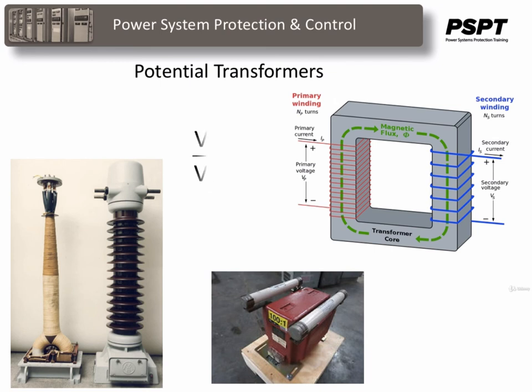Potential transformers. In general, the secondary voltage is proportional to the ratio of the turns and opposite in phase to the primary voltage. This relationship is not completely exact for the following reasons. The exciting current that is necessary to magnetize the iron core causes an impedance drop in the primary winding. The load current that is drawn by the burden causes the impedance drop in both the primary and secondary windings. Both of these produce an overall voltage drop in the transformer and introduce errors in the ratio and phase angle.